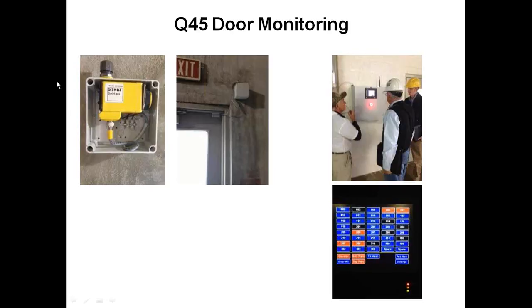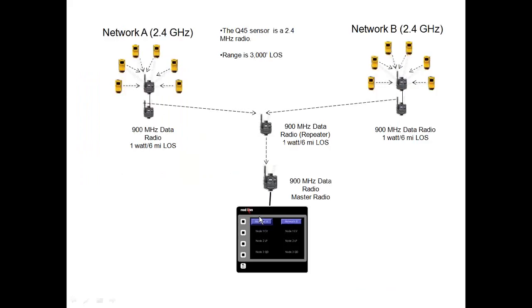This next one only had about a 3,000 foot range, but they had multiple buildings, so we put together a hybrid system worth talking about. With these data radios, we can have little nodes out here feeding a gateway, and also use what we call a data radio — just a 232/485 serial radio. The gateway collects all this information, and using a splitter cable we connect to the data radio, which looks at the Modbus registers and transmits them. What's neat is this family is 2.4 gigahertz so it can be sold globally.